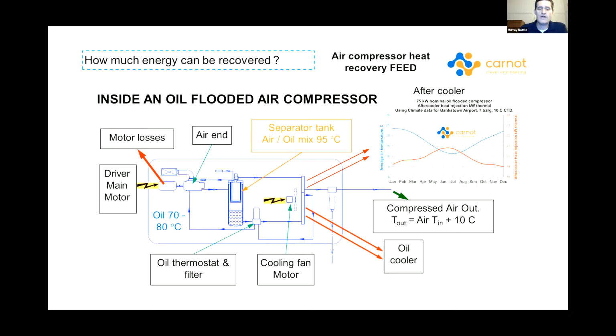As far as where all the heat comes and goes, probably 85 to 90% of the energy is provided to your main drive motor. Of that, 5% is lost due to motor efficiency losses. If you've got a VSD, that'll add another 2 to 5% in the electrical losses going to the drive motor. And you've got your cooling fan motor as well. That will use between 2 to 5% of the compressor's nameplate power. So you'll reject 70 to 80% of the heat to your oil cooler and 20 to 30% to your aftercooler.